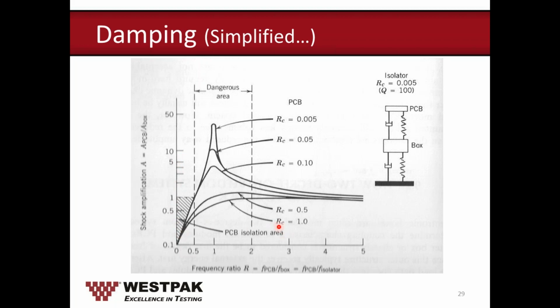So what this tells us is that when we have a damping ratio, R sub C, equal to 1, the system doesn't amplify at all at its natural frequency, and returns to a relatively benign, or 1 to 1, ratio as soon as the excitation is removed. As the damping ratio gets less and less, we see amplification at this level, and at one of the lower, less desirable damping coefficients, R sub C of 0.005, the amplitude of the response can be in the neighborhood of 10 to 50 times the input. That's in what we call the dangerous area. So a well-damped system is going to have a relatively low level of response here, and ideally at 1, but we almost never see that.